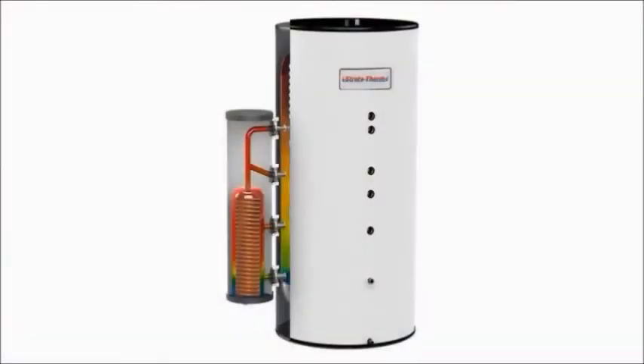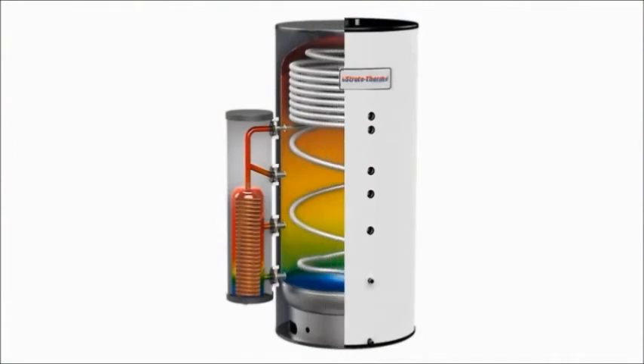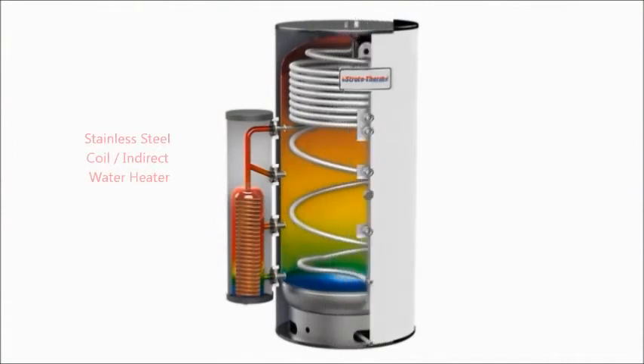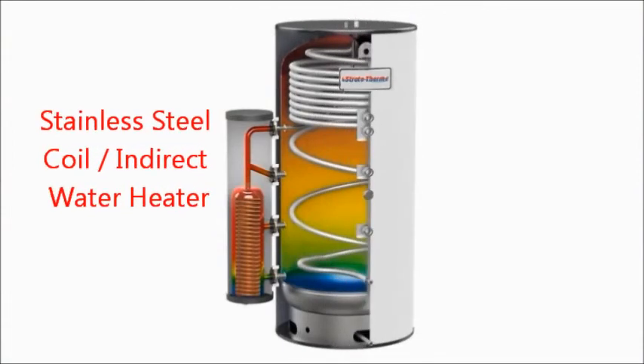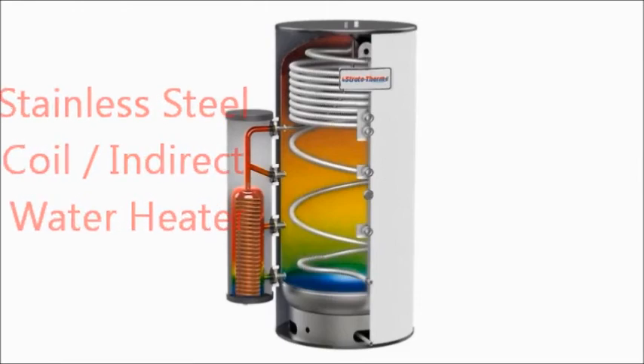Well, Paul, the large diameter stainless steel coil internal to the tank contains potable water, which is indirectly heated via solar thermal and boiler backup BTUs as the water passes through the inside of the coil. This reverse indirect water heater design can provide continuous draws of over 2,100 gallons per hour. Interesting. Jeff, this tank is truly placing Lochinvar in a leadership position for easily integrating the production of domestic water, the buffering and hydraulic separation of space heating loads, all the while optimizing the efficiency of solar harvesting. I'm glad you see it that way, Paul.